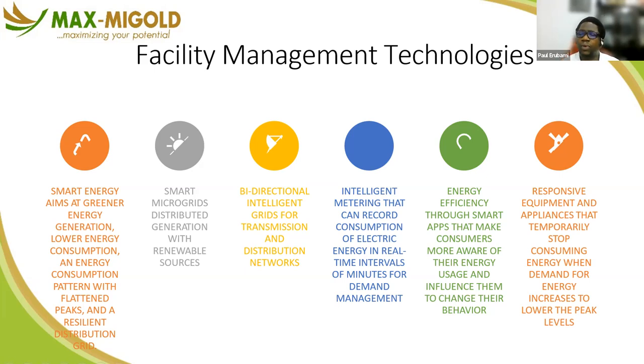Nowadays, we have renewable systems embedded with your fossil fuel system. You can have your solar panels installed, and they are synchronized with your generators in the same array, such that the generators don't kick in until the solar panels during the day have satisfied their load consumption. What the solar panels cannot take, the generators will take, right? And as the load increases, the generators can come on one by one. And then you don't even have to have batteries because of this technology.